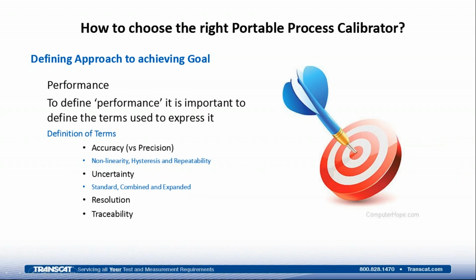So in order to properly define performance, it's important that we define the terms used to express it. So we'll talk about, as I said before, accuracy, and also want to make a comment about precision and what that means and how it differs from accuracy. And the components oftentimes discussed in the definition of accuracy: nonlinearity, hysteresis, and repeatability. Then talk about uncertainty, different kinds or levels of uncertainty: standard, combined, and expanded. Quick word about resolution and traceability.